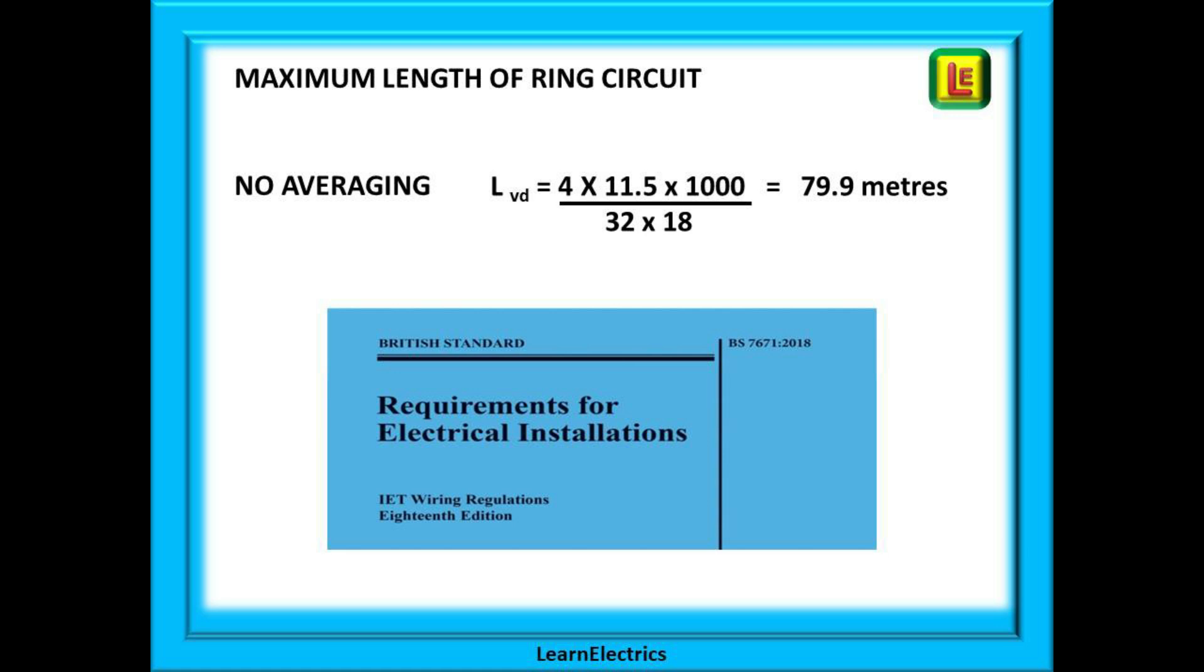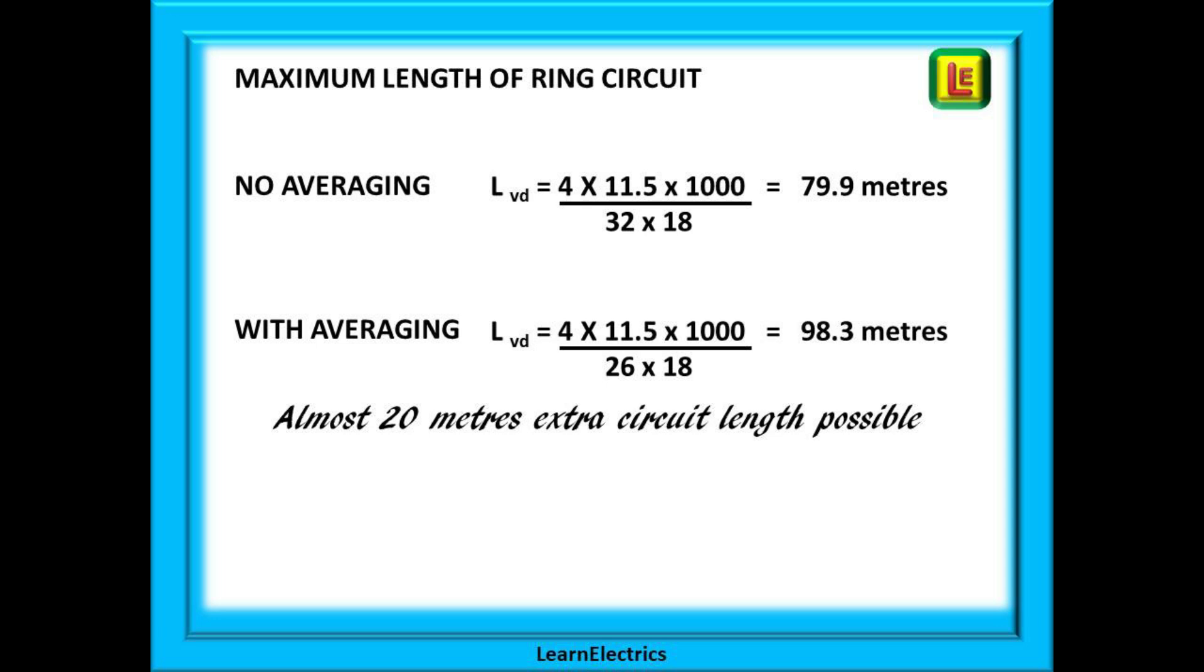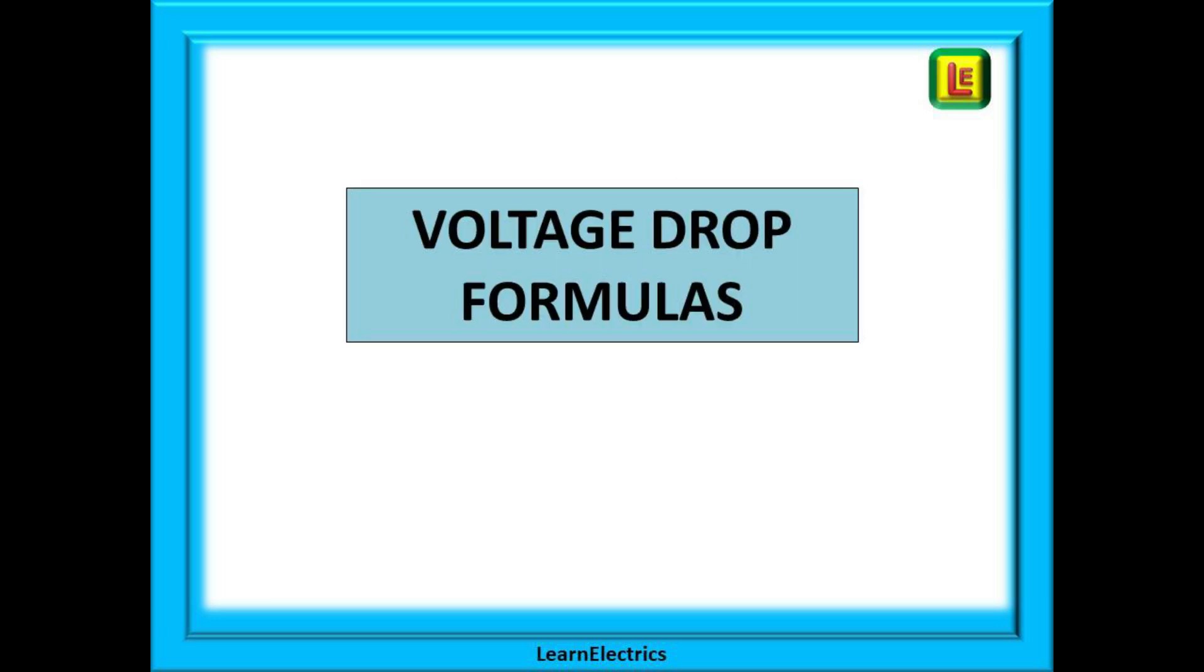We'll do the same calculation but this time with the average load current, the 26 amps that we calculated previously. 26 amps replaces the 32 amps and we have a maximum length this time of 98.3 meters. This is almost 20 meters extra circuit length possible, a 25 percent increase. Hopefully you can see the significant benefit to using averaged load currents to maximum load currents.